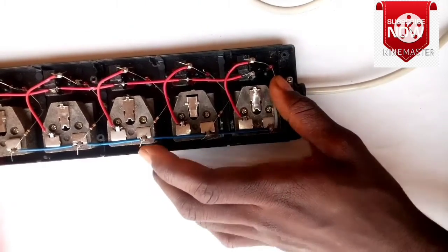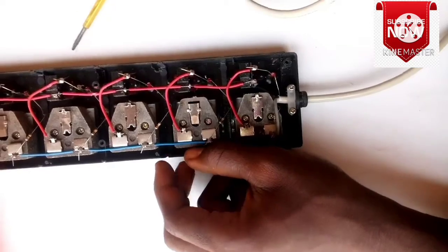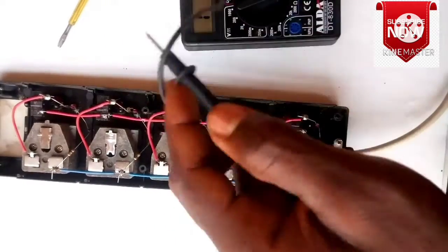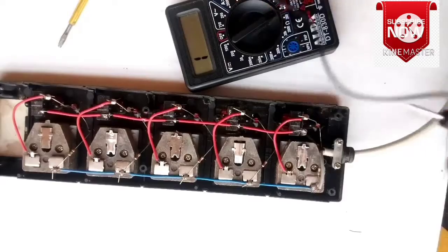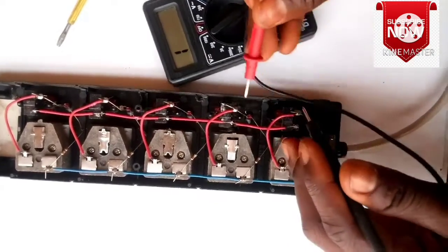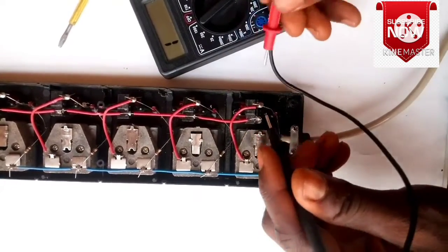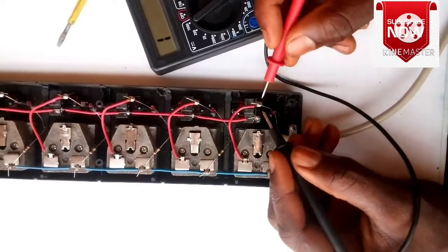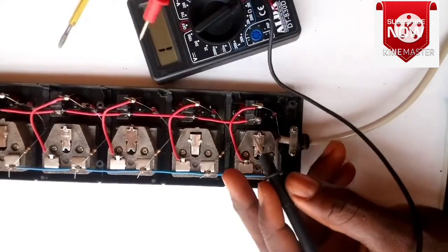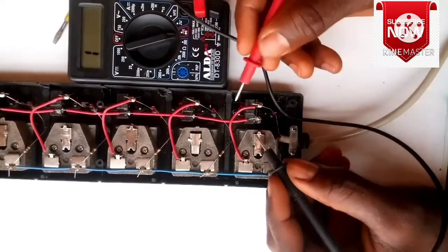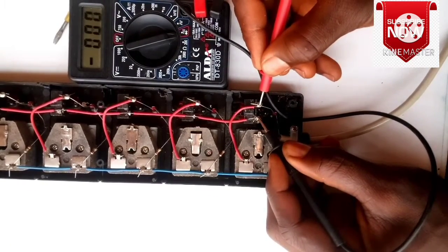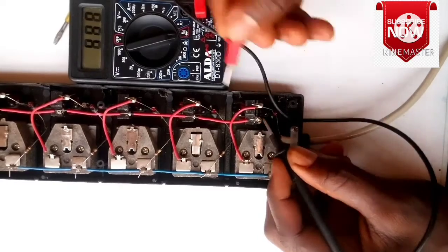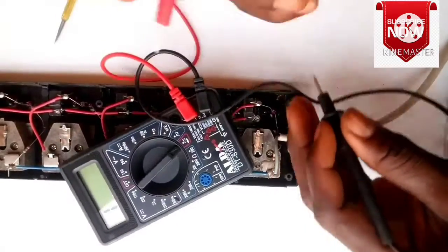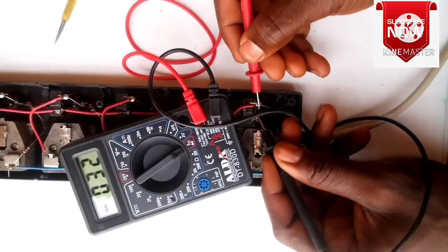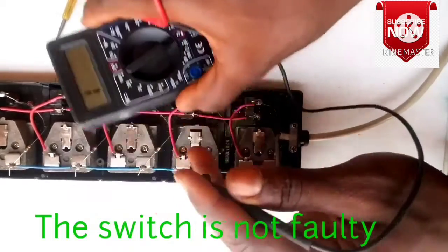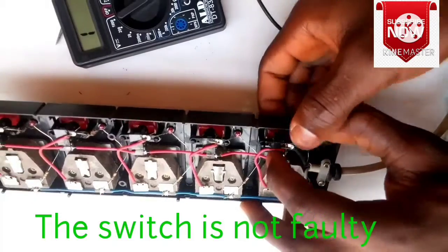But before even testing this cable, let's test the switch, because if the switch is faulty, we might start thinking it's the cable, meanwhile it is not. Let's test this switch. So what we'll now do is to connect the test lead to this switch here. So if it is continuous, then the same action is going to take place. So you can hear the sound of the multimeter, and the display shows that this switch is continuous.